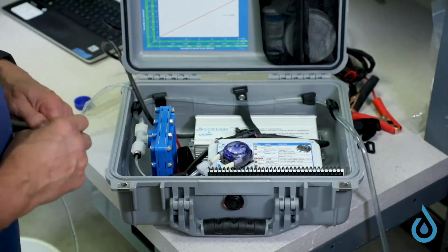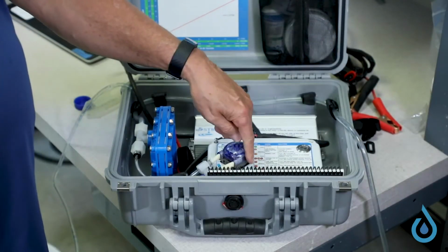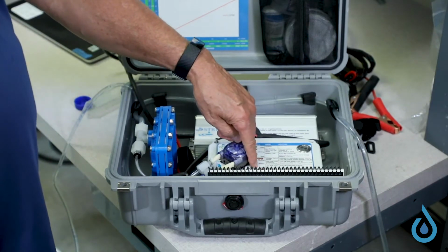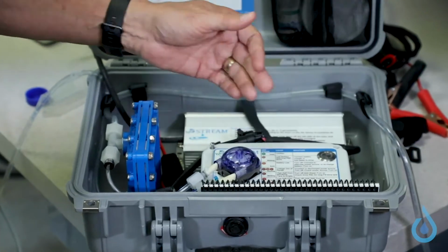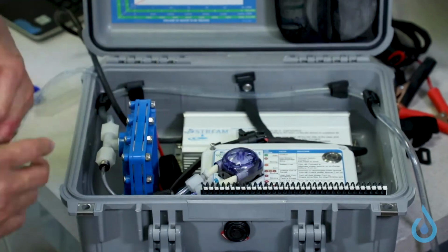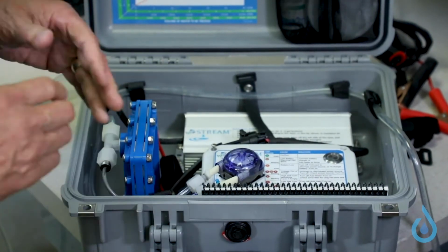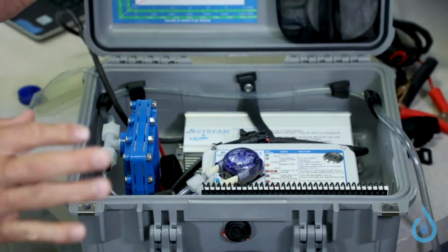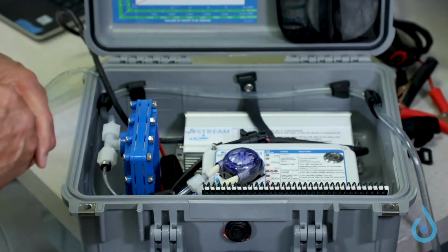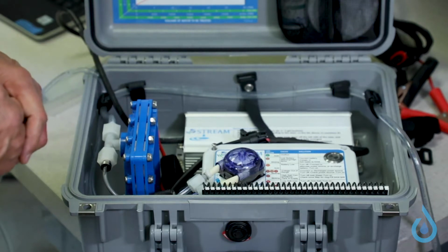In this diagnostic segment, we're going to talk about the flashing red, green, red. It's the last error fault on the chart. And this occurs when the system has overheated. And there are a couple of conditions that will occur to cause it to overheat.